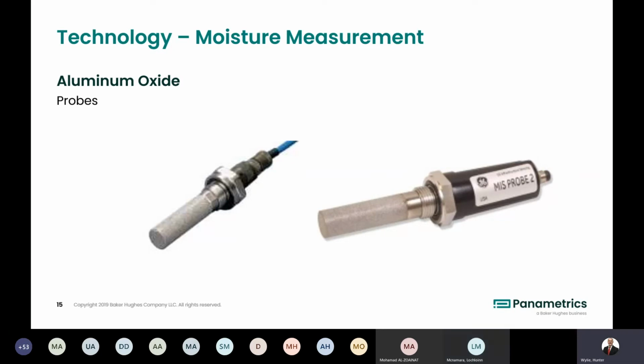So we have a few more discussions that have been going on in regards to the LDLs of Aurora and when it could be used in, it looks like, LPG applications as well as moisture in liquid hydrocarbons. So which question was that? Can Aurora be used to measure trace moisture in the LPG application? Yeah, the LDL of the Aurora is 2 ppm. So we can't really measure in that very, very dry application of less than 1 ppm. In the LPGs, we have to measure in the gas phase. I'm thinking of liquids, but yeah, 2 ppm is the LDL there, so we currently can't really measure below that accurately.